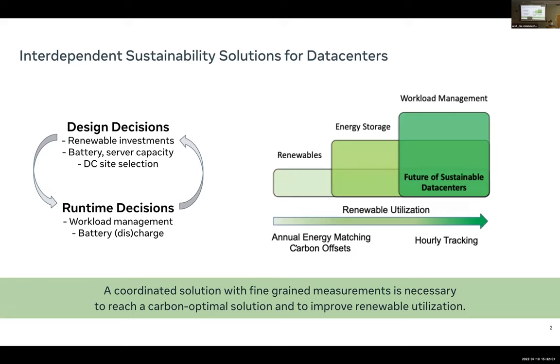Sustainability solutions for data centers are interdependent. These solutions include design decisions and runtime decisions. Design decisions such as renewable investments, battery capacity, server capacity, and data center siting are highly interdependent with runtime decisions such as workload management and battery charge or discharge decisions. Currently, the majority of technology companies invest in renewables based on annual carbon or energy matching, but this is not sufficient because of the intermittent nature of renewables. We need complementary solutions such as energy storage or workload management to improve renewable energy utilization and reduce carbon footprint further.